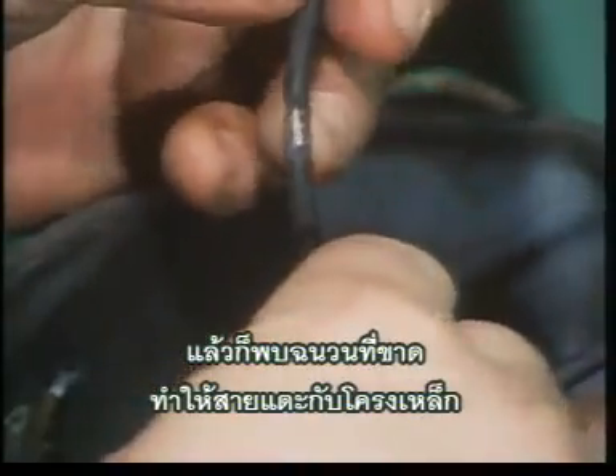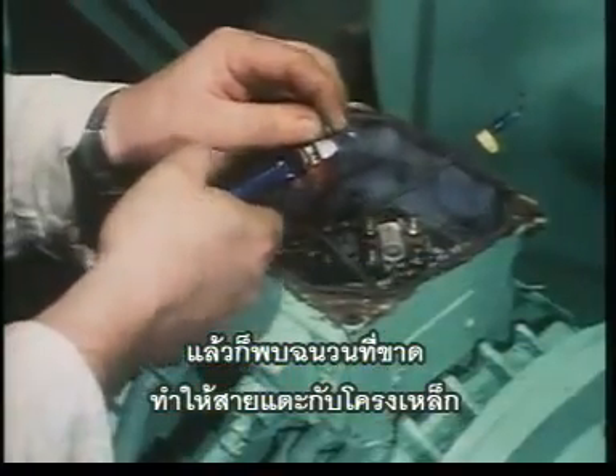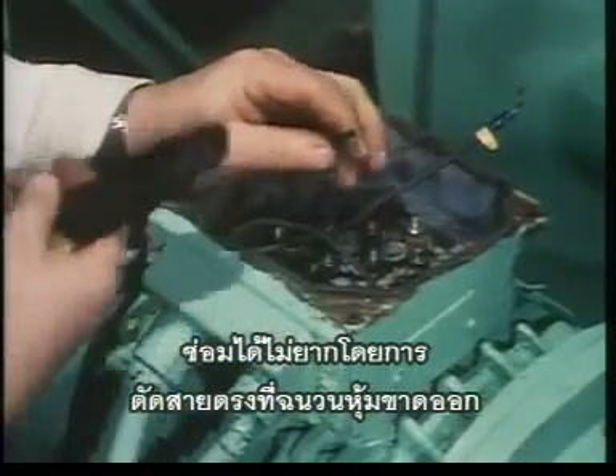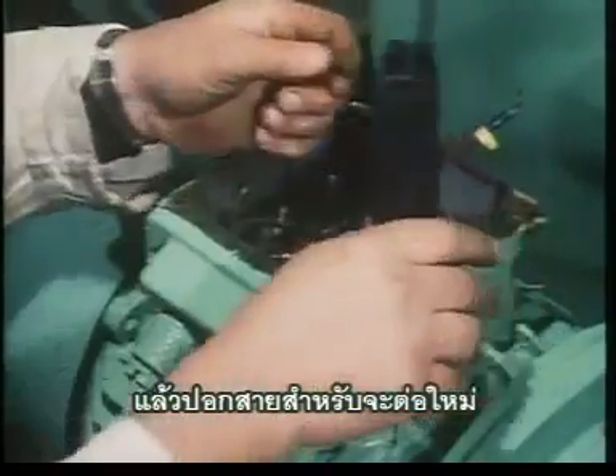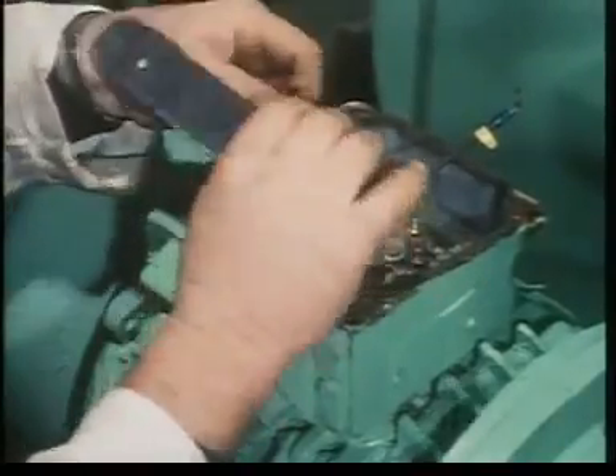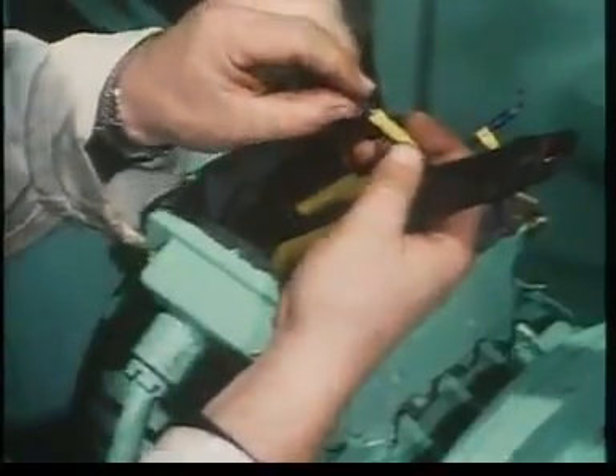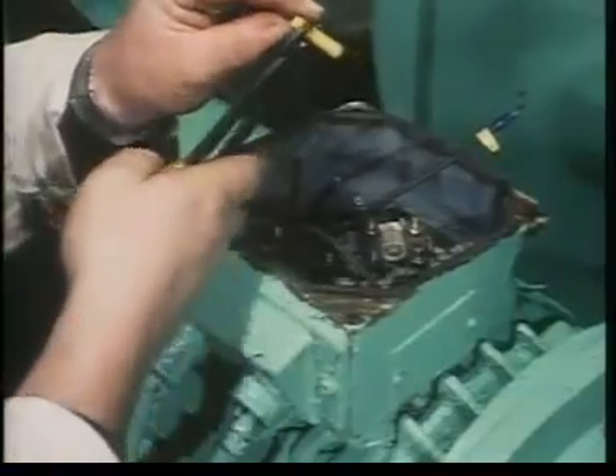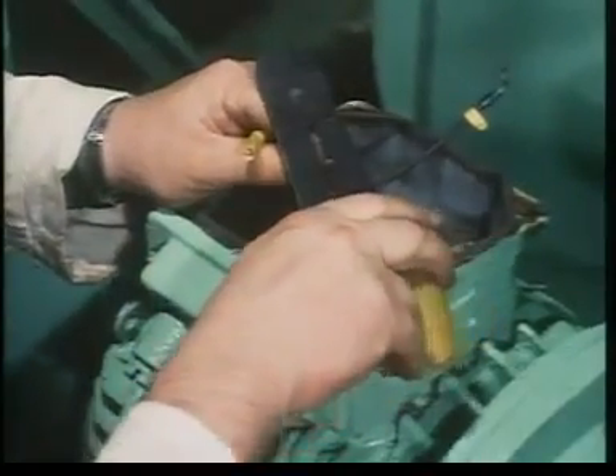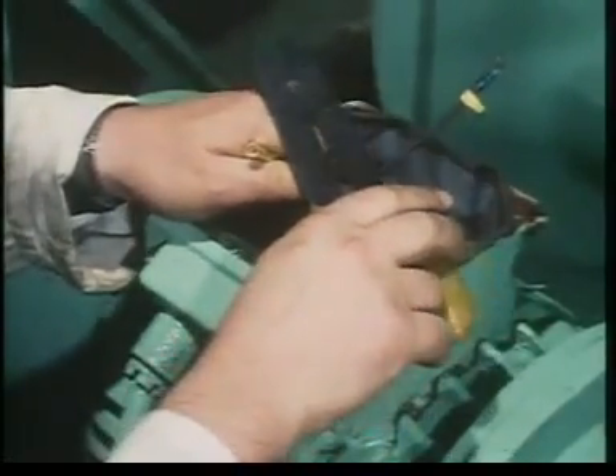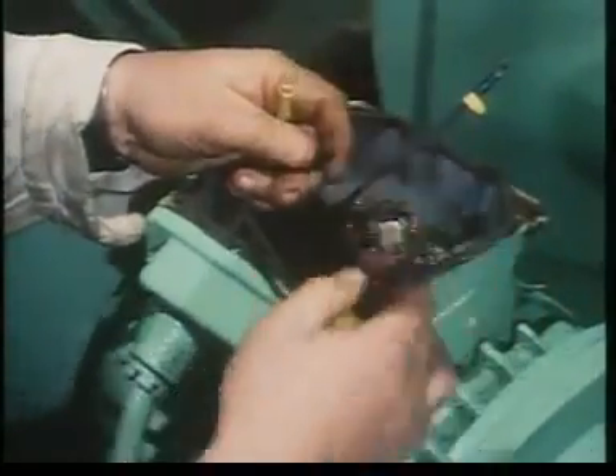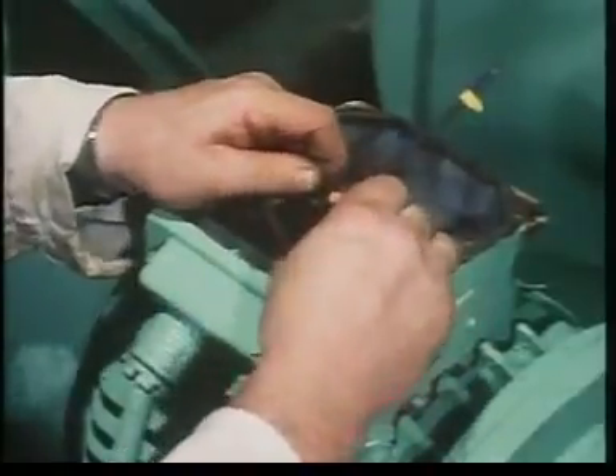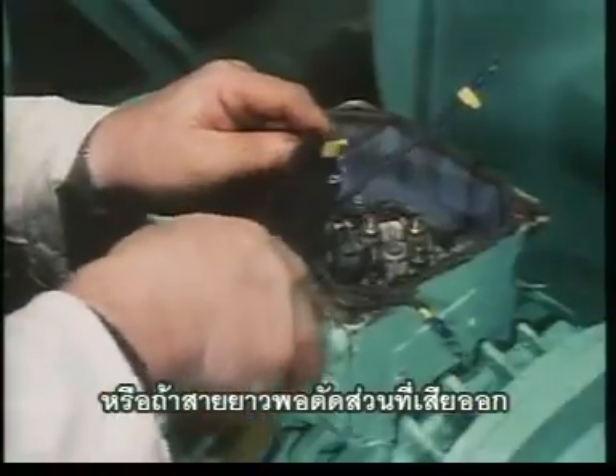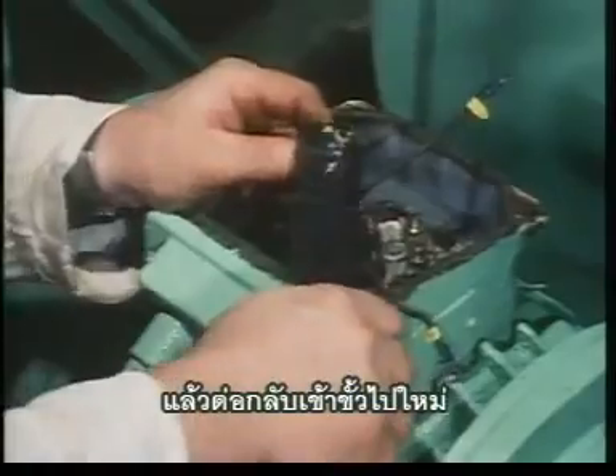And here you are. A break in the insulation has caused the conductor to touch the casing of the terminal box. The fault is quickly remedied by cutting the cable where the insulation is damaged and stripping back the wire for a straight connector to be fitted on both ends. Alternatively, if the cable is long enough, cut off the damaged section and reconnect the cable to the terminal.